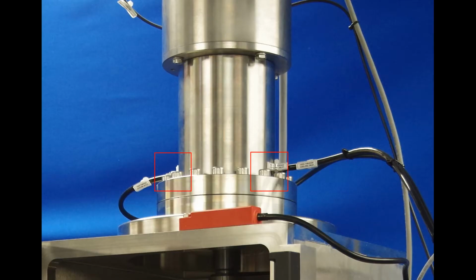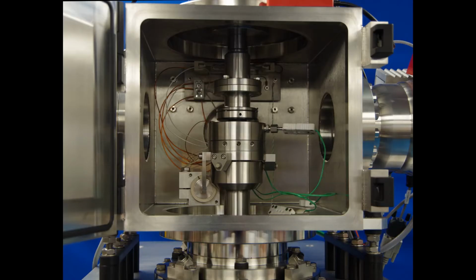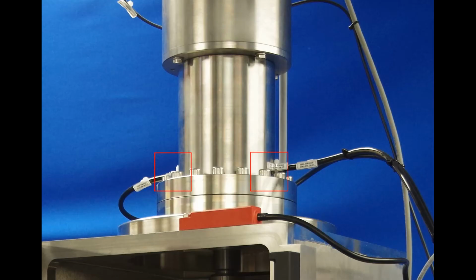The test spindle, which is in the form of a standard rotary feed-through, is fitted to the top of the chamber. Different hubs can be fitted to the spindle for different test configurations. There are a couple of ports on the feed-through for optional water cooling. These ports are connected to a manifold on the back of the machine. The feed-through is driven by a servo motor. There is an earth cable which forms part of the electrical contact resistance circuit.